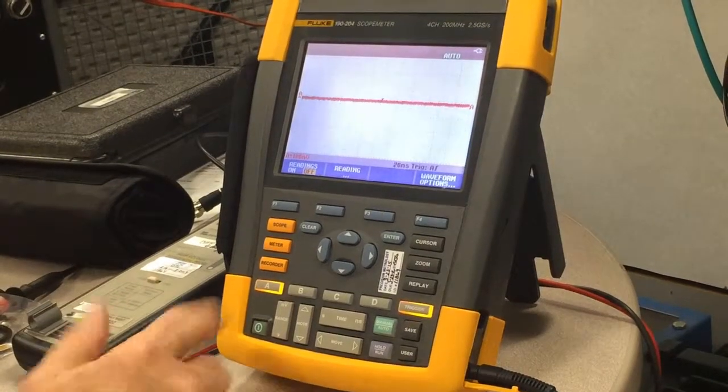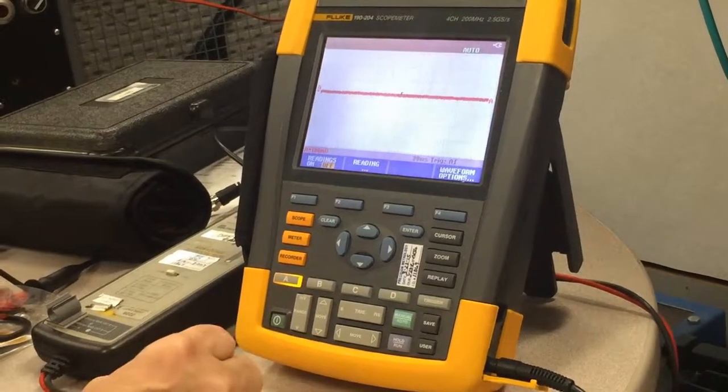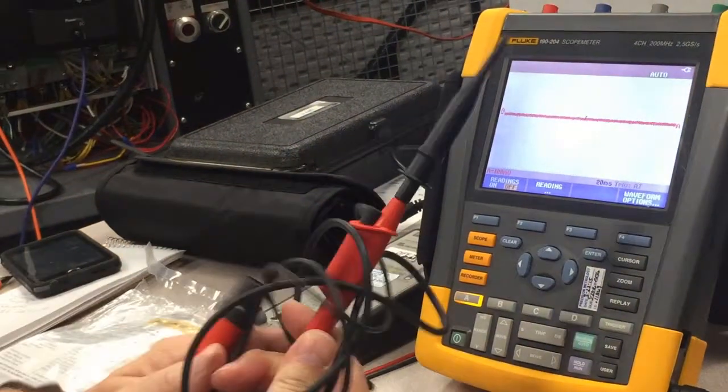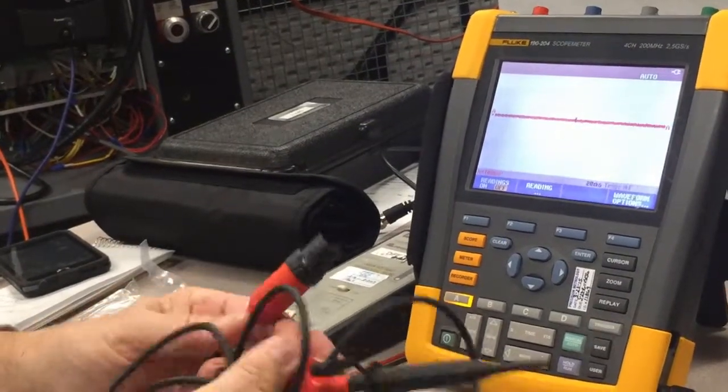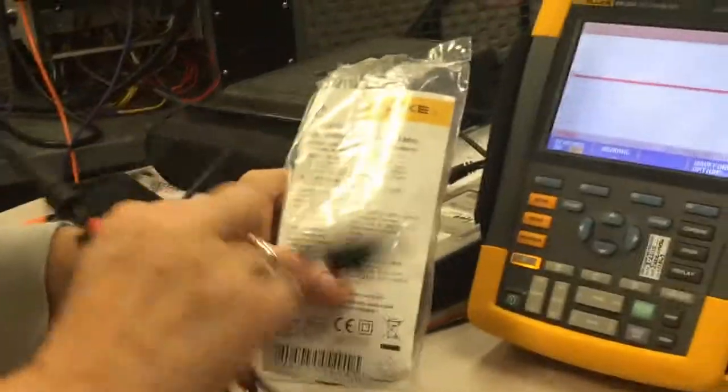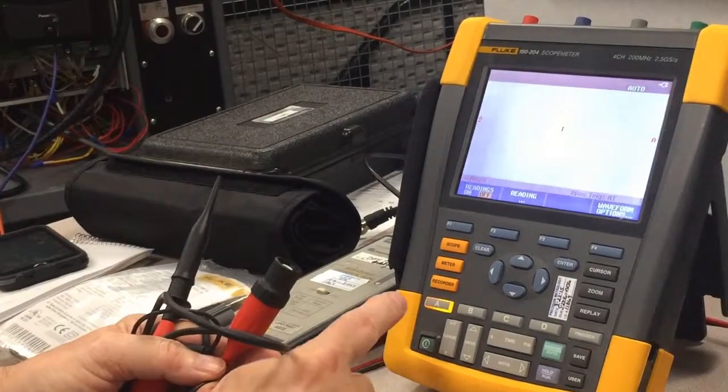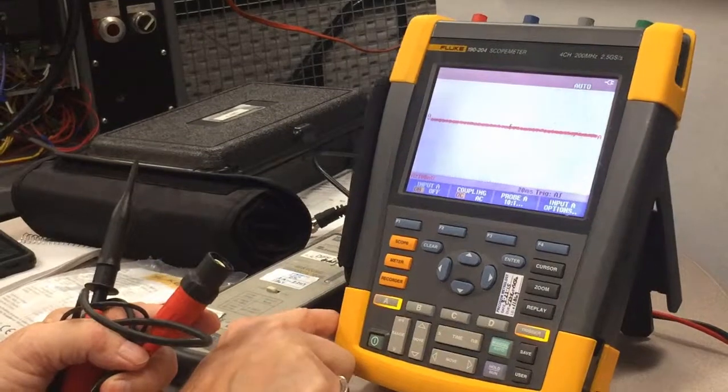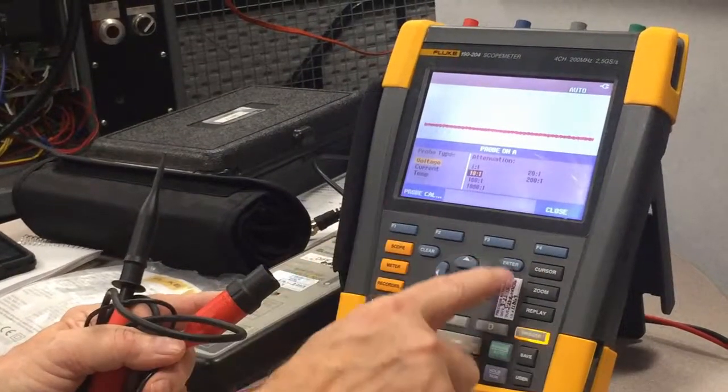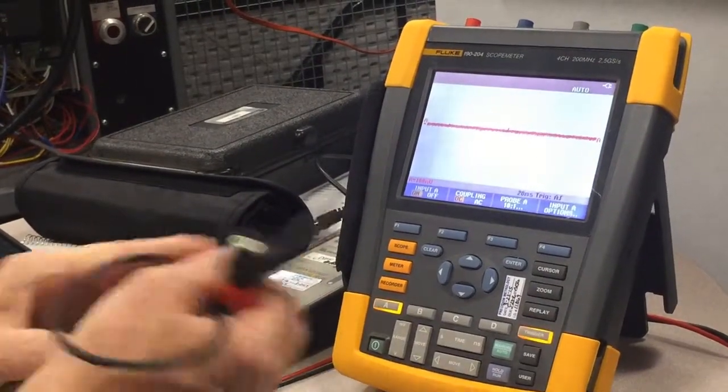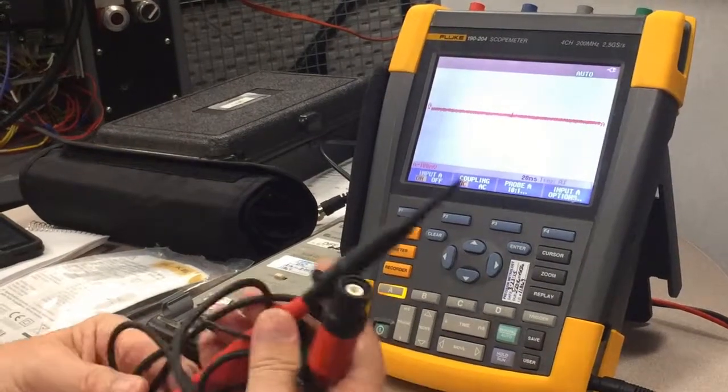The next thing you're going to do is set up for the voltage probe that you're using to measure the reflective wave voltage. The simple option is use the scope probe that comes with the Fluke scope meter. This scope probe has a 10 to 1 attenuation. So knowing that it's a 10 to 1 attenuation, and we're going to connect it to channel A, we press Channel A, and we go to the scope probe attenuation, and then we make sure it's set for 10 to 1, and then press Enter.